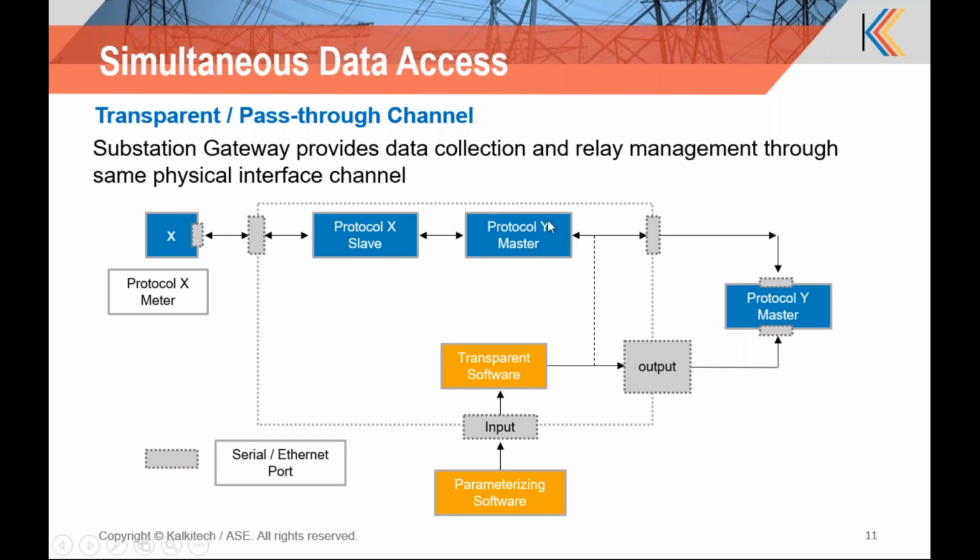Now, this Y can be associated with a transparent channel, which is linked to the parameterizing software, either through a TCP channel or a serial channel. And then once this parameterization software gets connected to this channel, the data will be available onto this channel, and this protocol Y master will temporarily store and allow the messages from the transparent channel to pass through the same port, and the response back to the parameterization software.